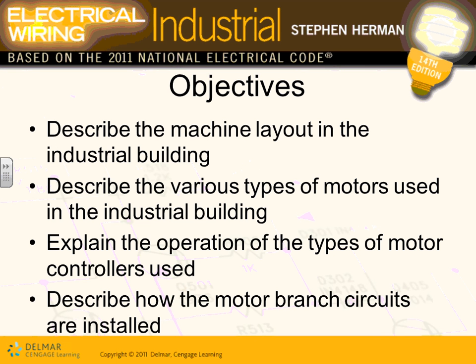The most common type of motor that we use is the induction motor, the three-phase induction motor. Everybody knows that one. But then we have a DC motor, and we have the wound rotor motor. We'll say a few things about these. And of course, the single-phase induction motors. If you have a commercial building, typically we don't use a whole lot of them. Operation of the types of motors and motor controllers. Motor branch circuit and installation.